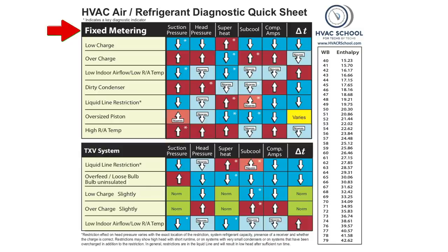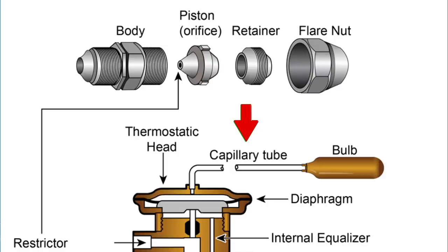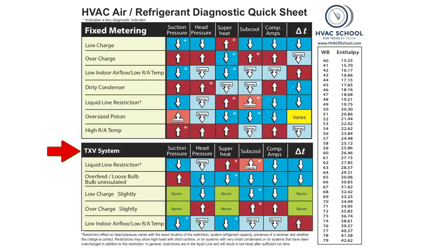If you take a look at this chart up top, we have a fixed metering device type of system, and then a TXV system below. We're focusing on low indoor airflow and low return air temperature. The chart up top is for a fixed metering device — a piston or capillary tube — and below are the symptoms you see for a TXV system.